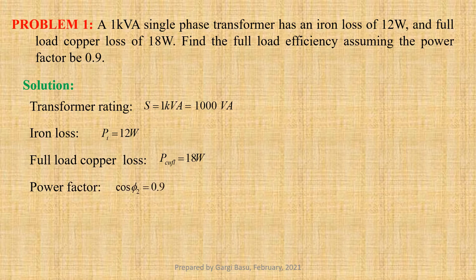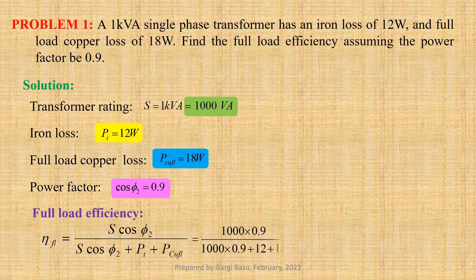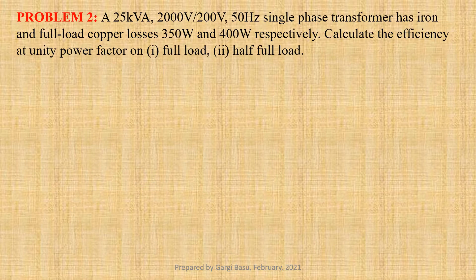We know that the expression for full load efficiency: ETA_FL equals to S cos phi 2 divided by S cos phi 2 plus P_I plus P_copper_FL, that is equal to 1000 into 0.9 divided by 1000 into 0.9 plus 12 plus 18, that gives us 96.77 percent.